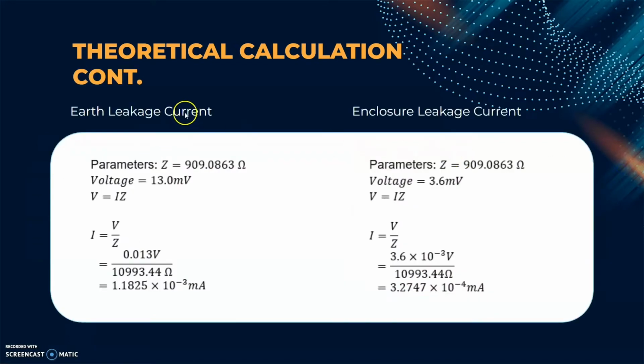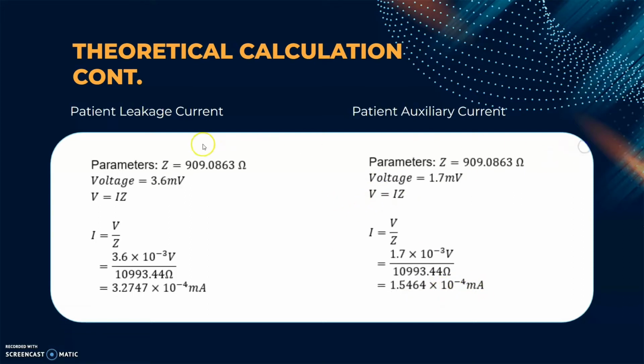To find the leakage current, using the formula V equals IZ, we insert the voltage that we get from the experiment and the impedance that we calculated. So we get 1.1825 times 10 negative 3 milliampere. For enclosure leakage current, we get 3.2747 times 10 negative 4 milliampere using the same formula. For patient leakage current, using the same formula also, we got 3.2747 times 10 negative 4 milliampere. And for the patient auxiliary current, same formula, we got 1.5464 times 10 negative 4 milliampere.